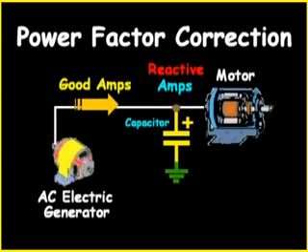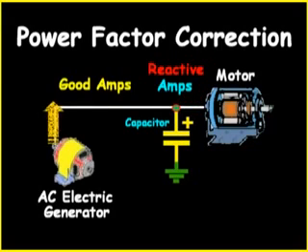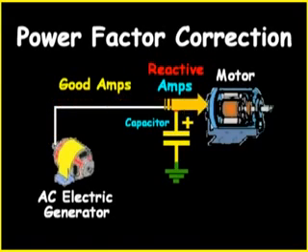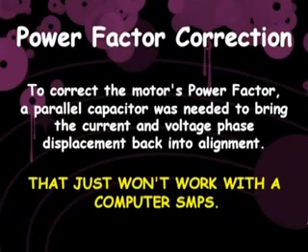To stop the reactive amps from flowing in the electrical wires, a capacitor is placed in parallel with the motor. The reactive amps now flow back and forth between the capacitor and the motor. This resonance prevents reactive amps from flowing in the connecting electrical wires. To correct the motor's power factor, a parallel capacitor was needed to bring the current and voltage phase displacement back into alignment.